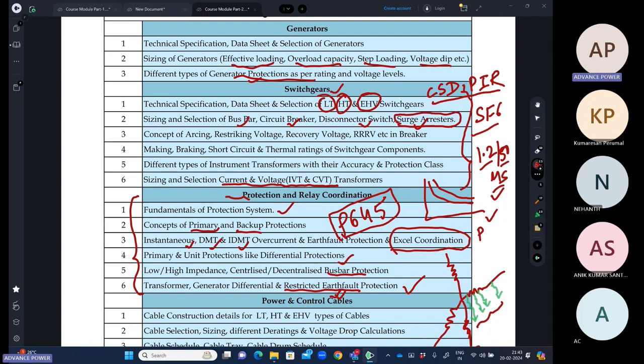You will be able to know that the power frequency withstand voltage is not required to be coordinated with the surge arrester. This is only a parameter which is to be withstood by the surge arrester. So all these phenomena we will discuss, different types of wave shapes, where they happen, what the durations are, and how the arrester is selected. So in detail from LT, because we use surge arresters in motor feeders also, we use them in EHV systems also.